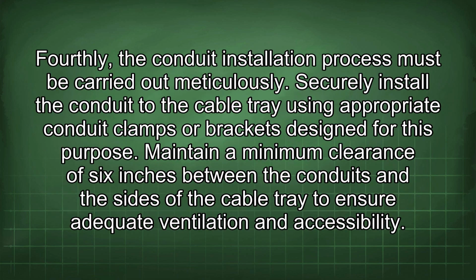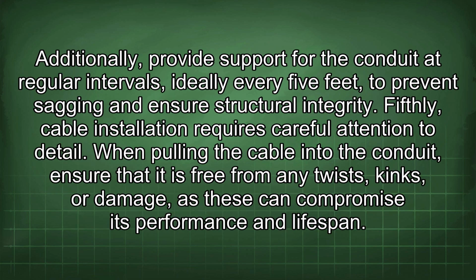Fourthly, the conduit installation process must be carried out meticulously. Securely install the conduit to the cable tray using appropriate conduit clamps or brackets designed for this purpose. Maintain a minimum clearance of 6 inches between the conduits and the sides of the cable tray to ensure adequate ventilation and accessibility. Additionally, provide support for the conduit at regular intervals, ideally every 5 feet, to prevent sagging and ensure structural integrity.